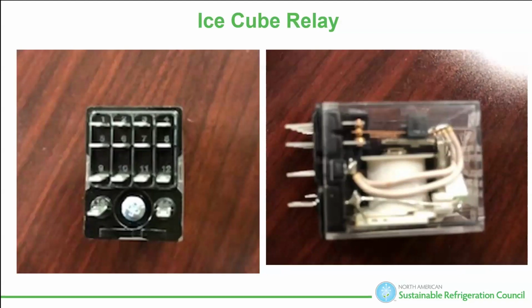That's important for us. Don't do like me. I was troubleshooting a circuit one time in my own training room. I had a relay bad, and like every other mechanic on the planet, I figured I'd just get the relay next to it and pop it in to check if it was good. I did, and I went, oh man, 2 bad relays in one little circuit, this is stupid. Then I grabbed a third relay because the engineers who put it together must be stupid too. I popped it back in, and this time I saw the magic smoke leave. I looked at the coil and realized I'd just popped two 24 volt DC coils into a 110 volt base.